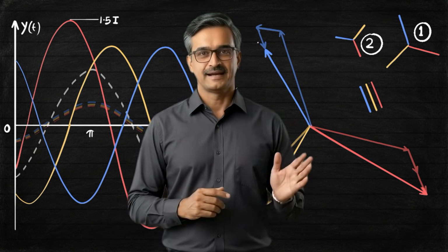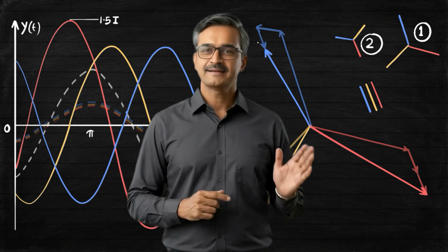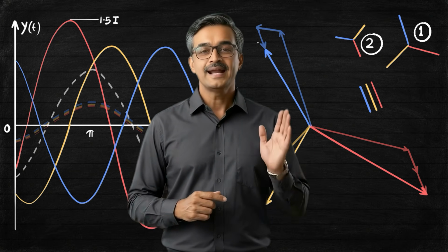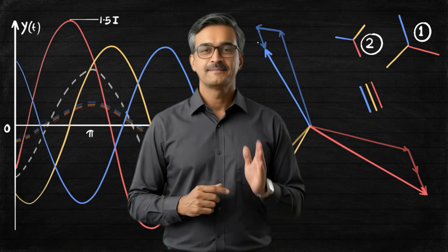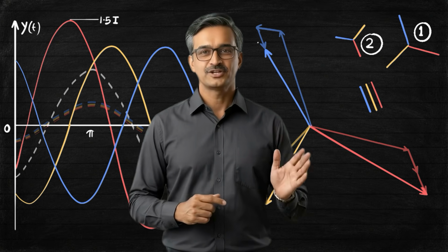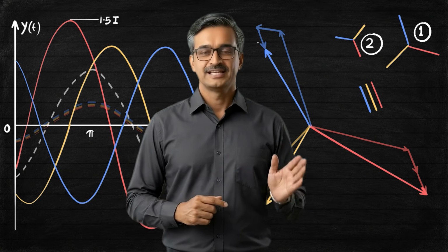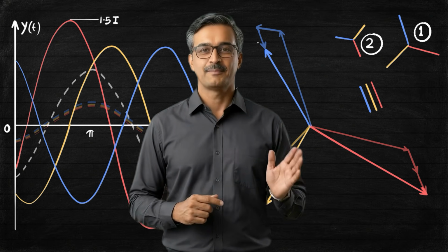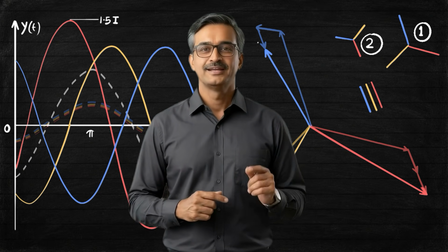For example, if the system is supplying a motor, this reverse rotating magnetic field can produce a counter torque and additional heating in the motor. So the combination of the forward torque produced by the positive sequence component and the opposing effect produced by the negative sequence component can create disturbance and heating in the motor during the fault.